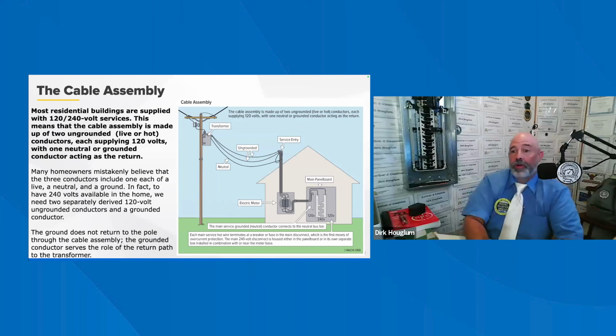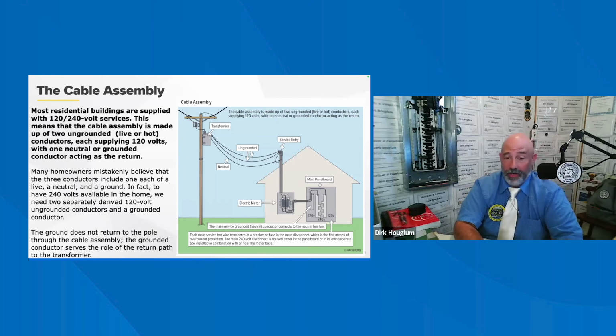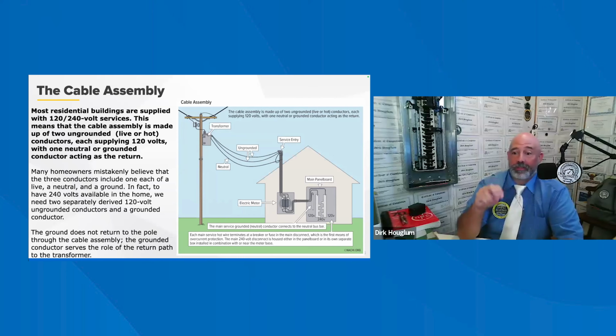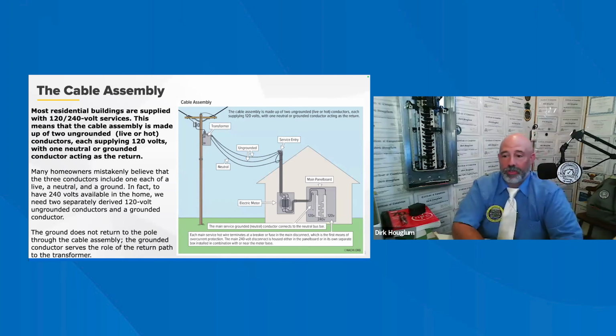Okay. So there are, however, a few variations on the theme. It is not unusual to see one of the live conductors tied back. This is indicative of a 120 volt only supply, which is still installed in some older properties, apartments, and condos. Conversely, the inspector may see cable assemblies with more than 3 connecting conductors. This is typically a 3-phase supply, commonly found in both commercial and agricultural environments. In this case, we recommend that the inspector report show this limitation. In the case of high voltage 3-phase supplies, we recommend that the inspector defers this part to an electrical specialist or an electrical contractor, for a qualified industrial or commercial inspection.